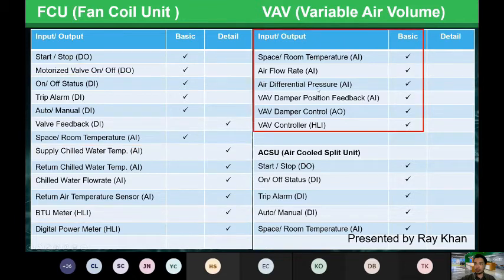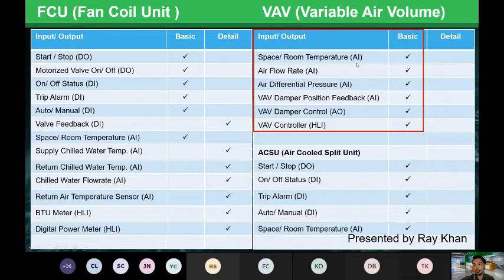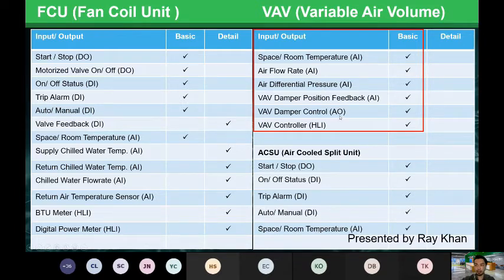For Variable Air Volume (VAV) systems, the VAV air controllers can run on BACnet, LonWorks, or Modbus high-level interface. Basic points needed for VAV systems include: air temperature input as analog input, room temperature, flow rate, differential pressure — all analog inputs — and the position of VAV dampers. Controlling the VAV dampers uses analog outputs.